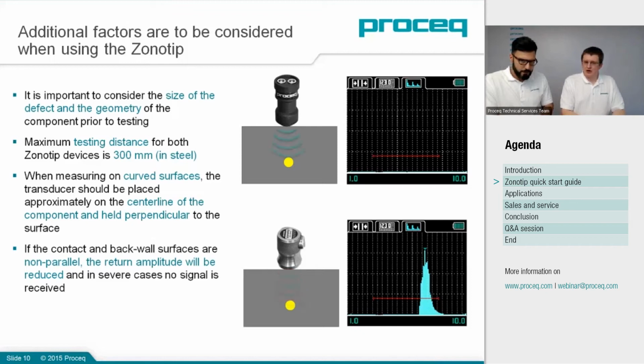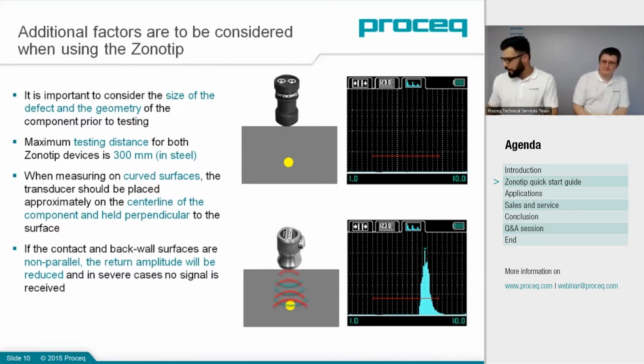And when measuring on curved surfaces, if you're using the twin, you should make sure it's aligned around the center line to get a good signal from both the transmit and receive elements. One of the main factors to consider, though, is if the front surface and the back surface are parallel. If you've got some area where the component is not parallel, the sound will bounce away and won't be received. In some cases, it will be received very low, or in the worst case, it won't be received at all. And then you can't use a thickness gauge for that. Great, thanks, Chris.